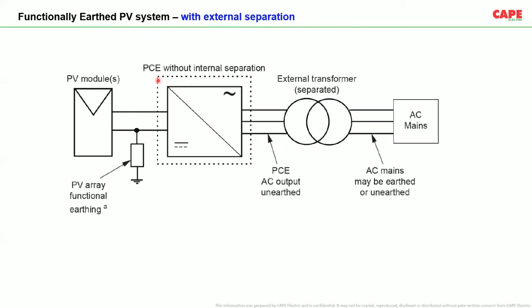One example is the functionally earthed PV system. I start from the left side. You have the AC mains, which may be earthed or unearthed. Then there is an external transformer. Just before the PCE, the power conversion equipment, or just before the inverter, you have a transformer which is electrically isolating the AC mains and the PV installation, including the inverter. Now the PV module, including the inverter, which is at the secondary side of the external transformer, is functionally earthed. You see here, this one, functionally earthed.